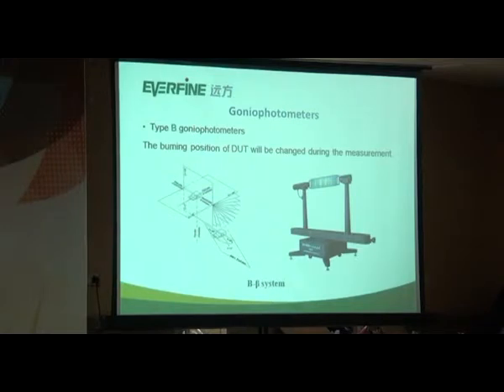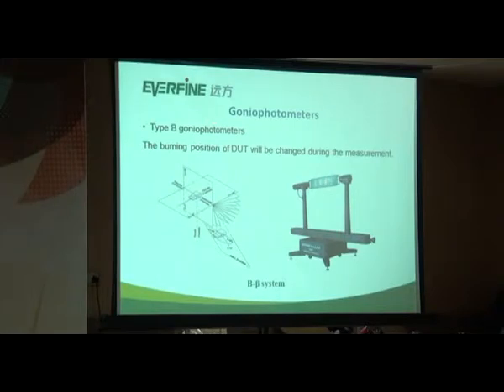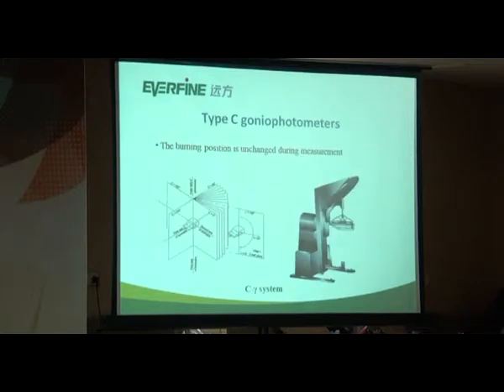This is a product of Type B gonio photometer. The sample will rotate here about this axis, so the burning position of the sample will be changed during measurement. As we know, burning position will influence photometric and colorimetric performance. So now more and more standards recommend using a Type C gonio photometer. For Type C, the sample will be mounted here and rotate around this axis, so the burning position of the sample will be kept unchanged, while the detector will rotate about this axis.